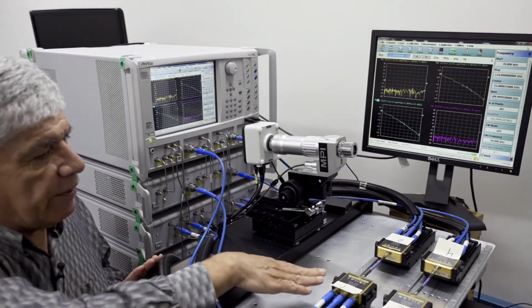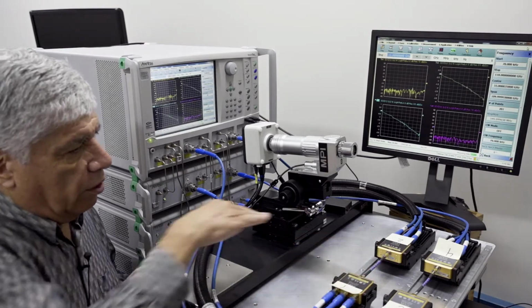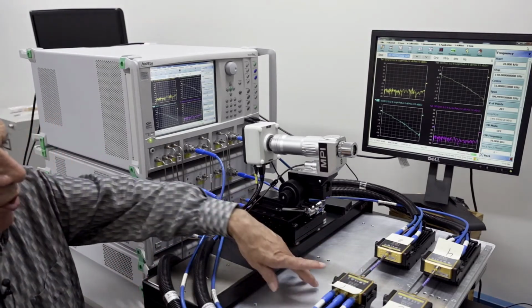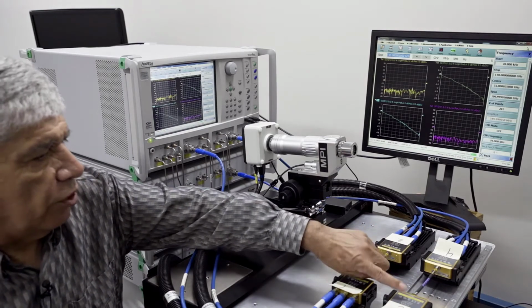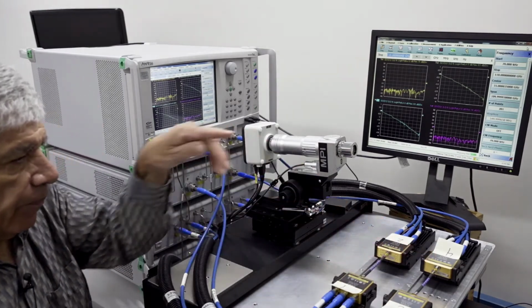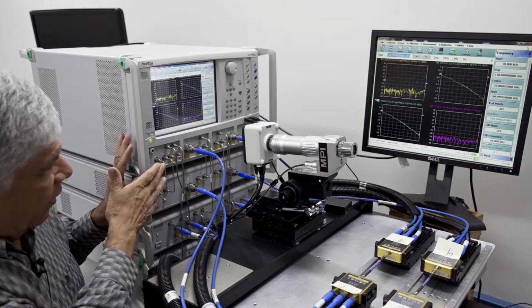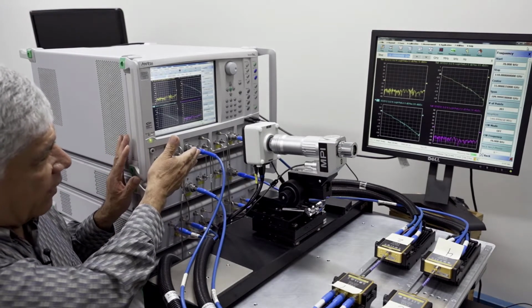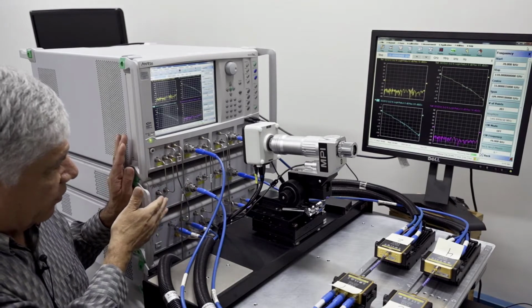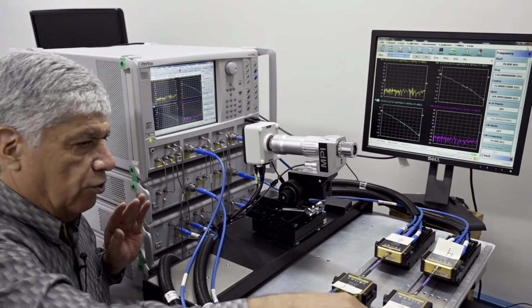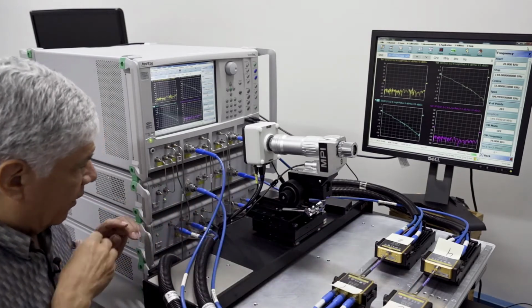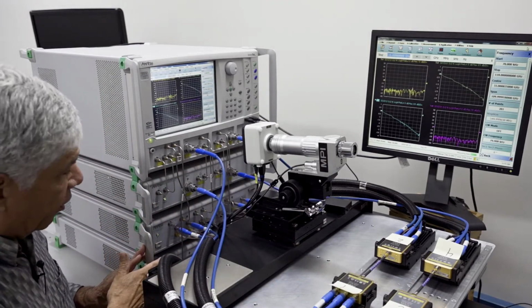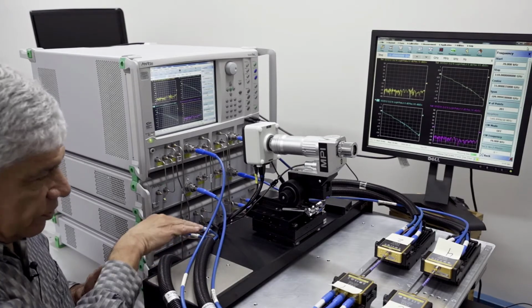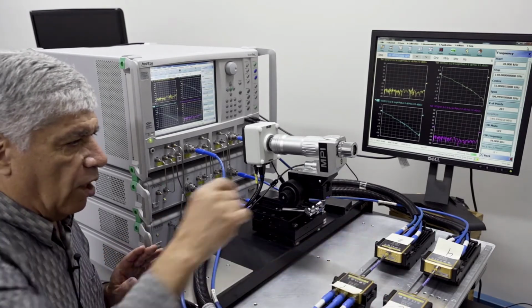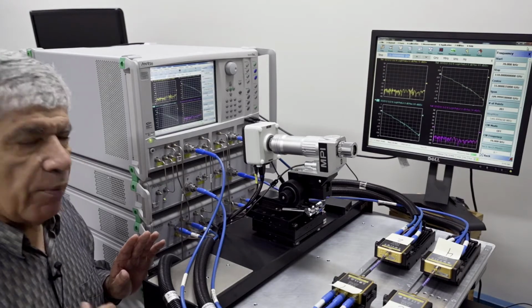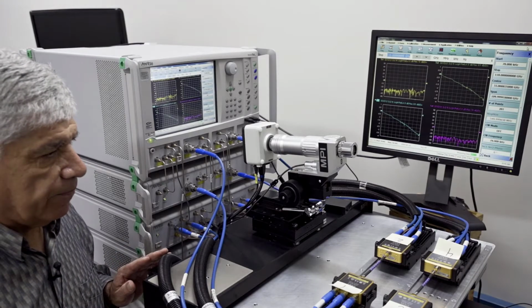And so you can see that we have our 4 millimeter wave modules, and I've labeled them for ports 1, 2, 3, and 4. And again, they're coming from the baseband VNA and the 4-port test set going to the module, and then switching over at 54 GHz, we have the RF and LO signals coming to the millimeter wave modules for operation up to 125 GHz.